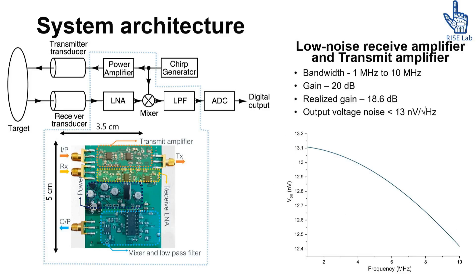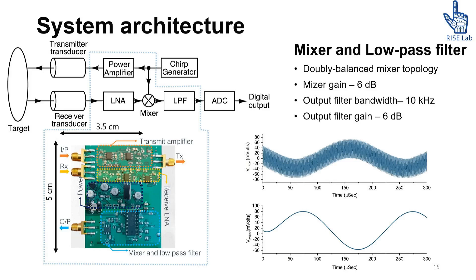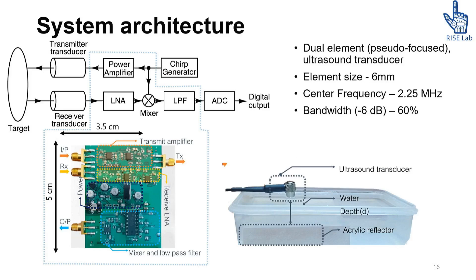I don't want to bore you with the details, but essentially we simulated and looked at the low noise amplifier and the transmit amplifier. We designed this to have a fairly large bandwidth for most applications, for musculoskeletal applications. We also made sure that the voltage noise is low enough for our applications. We designed the amplifier using the mixer using standard topologies, using a doubly balanced mixer topology, which gave fantastic results. And then we did some very simple pulse echo, reflector-based tests to see how we optimize the sweep time, right? So the sweep parameters in order to get the best image quality for our applications.